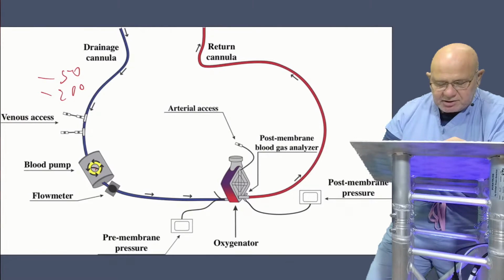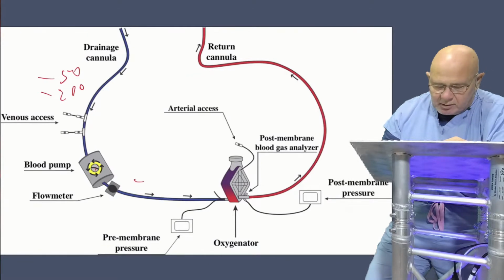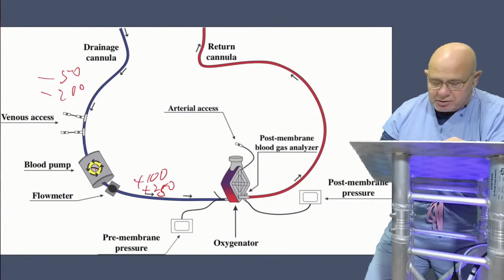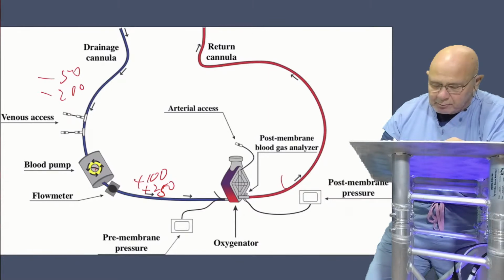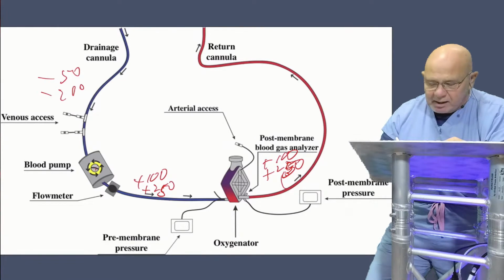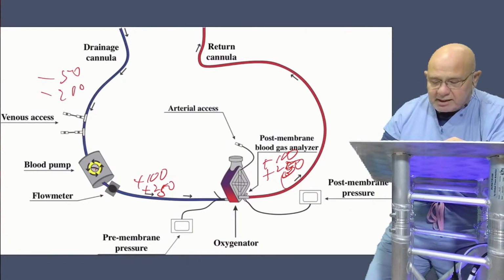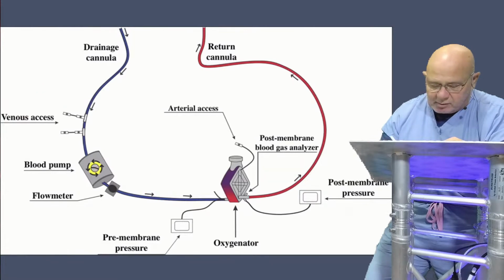Much like in the CRRT circuit, anything past the pump is going to be positive. This is going to be, let's say, positive 100 to positive 250. And then, of course, you have resistance through the membrane here, so the pressure here is going to be somewhere about plus 100, plus 250, but it's going to be a number that is lower than here. So let's look at that a little more in detail.